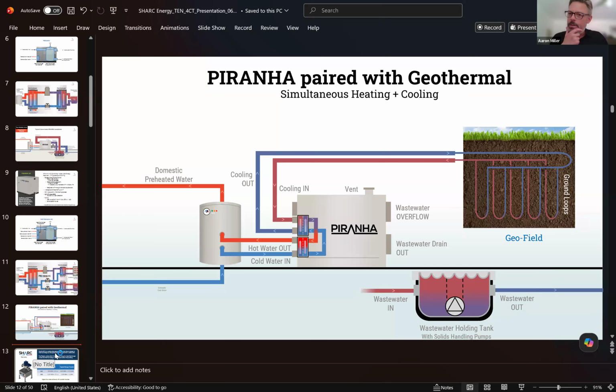This slide I've made for K through 12 schools in Maryland because every school put geothermal in under the soccer field because it was so heavily incentivized. The problem is schools are very cooling dominant in Maryland and very seasonal. So these geoloops were getting super saturated with heat and useless essentially. So what we're proposing is put a Piranha in, attach it to the ground loop, take some of that excess heat out of the ground loop to make hot water for the school, thereby bringing the temperature of the ground loop down so that all the other water-based assets on that loop, right, can operate in full capacity and efficiency.